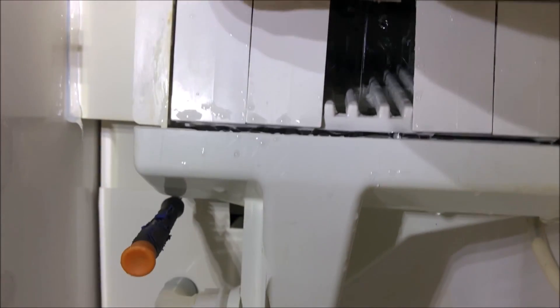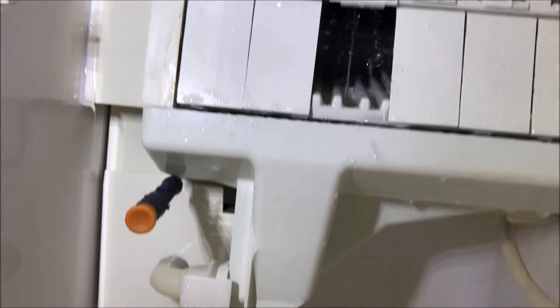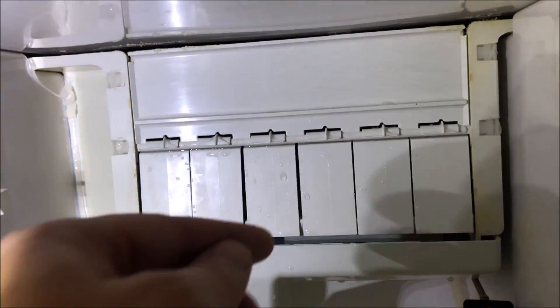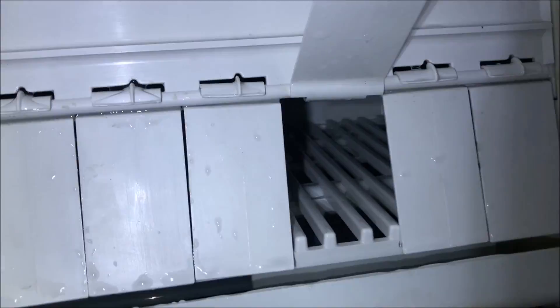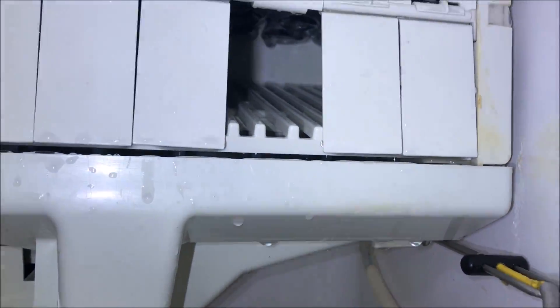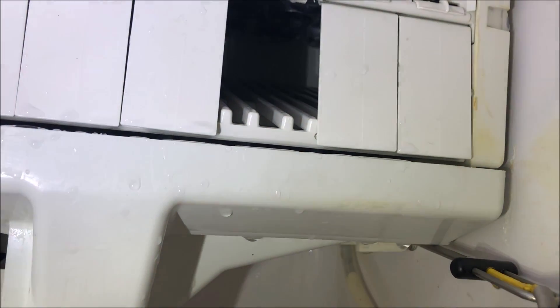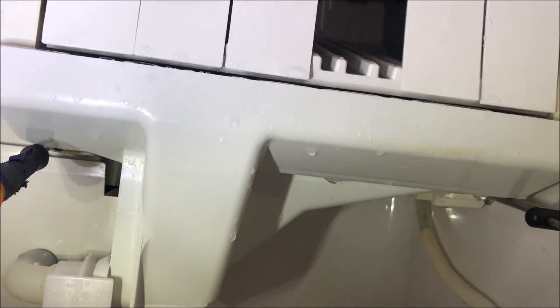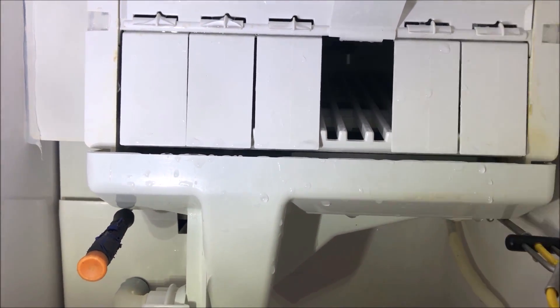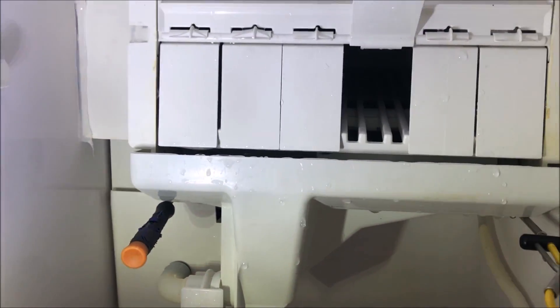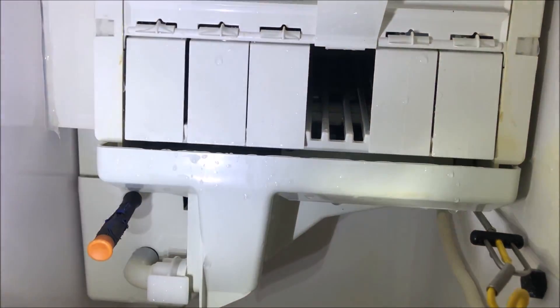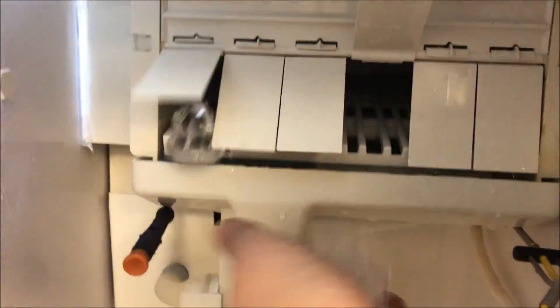We're 18 minutes in. The pump's still going strong. Remember last time I was 11 minutes in. And now we're going into harvest. Let's just pop open one of these little tabs here. Let's see if any ice drops out. And look at that. Just like magic. Ice dropping out. So our MacGyvering worked. The issue is this trough is not sitting on the track correctly and it's loose. As you can see, we're making great ice.